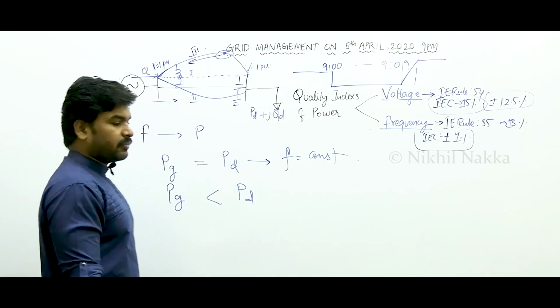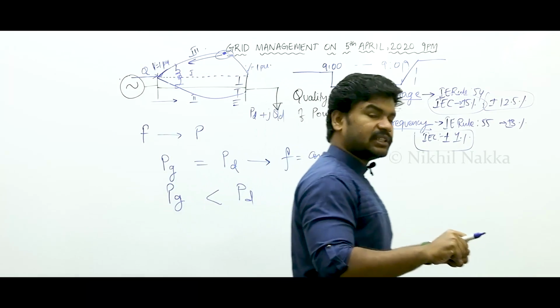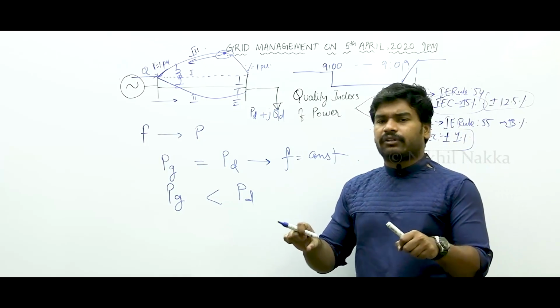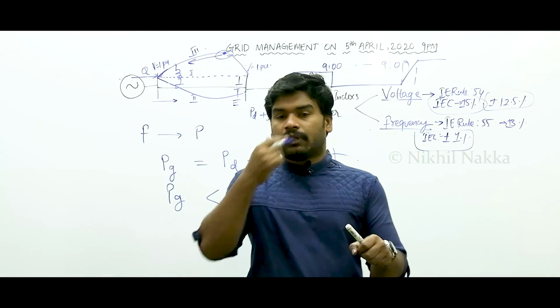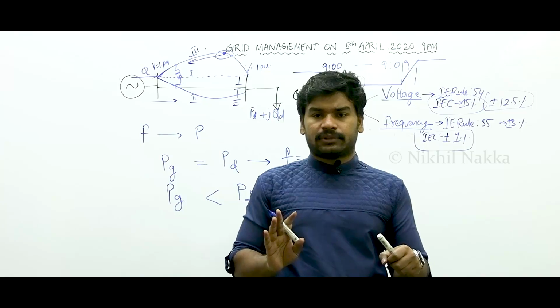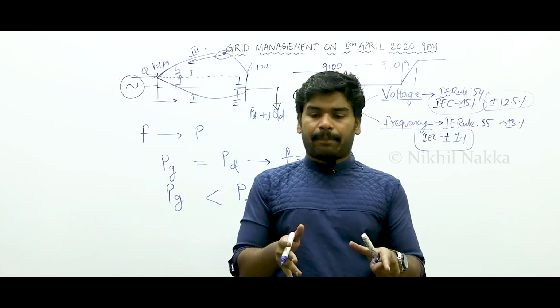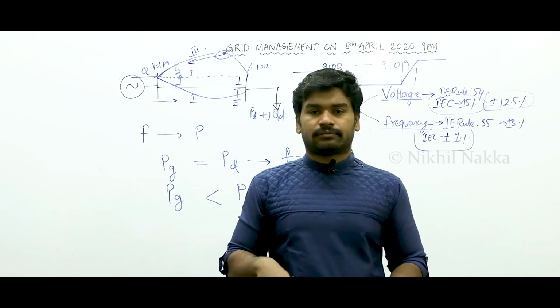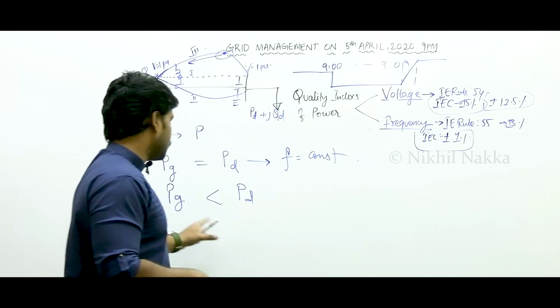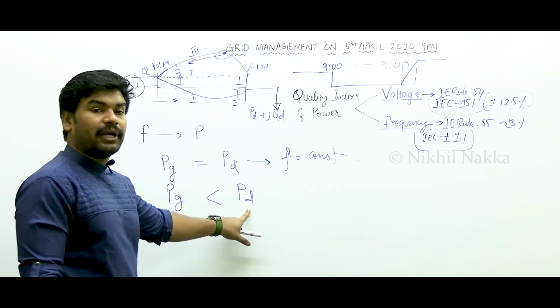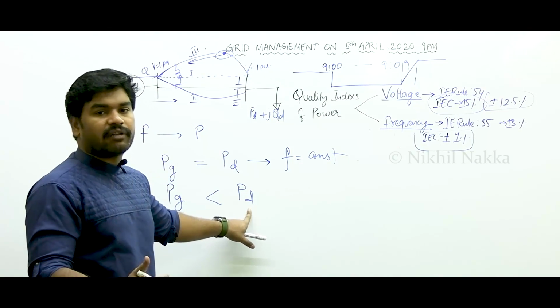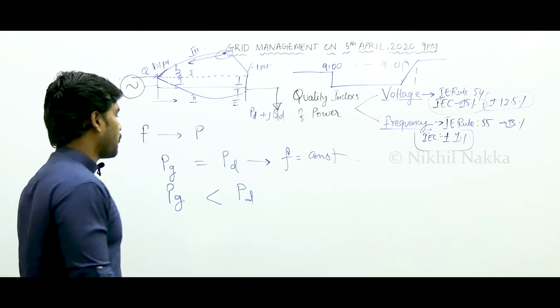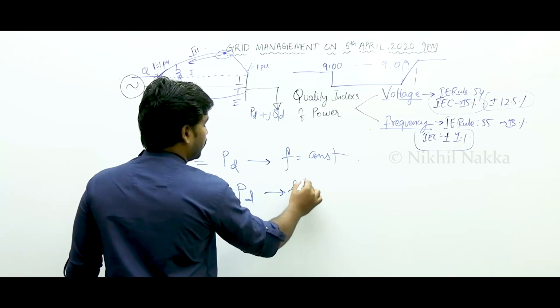More demand is there. Let us say you are going on a bike with constant acceleration, accelerator at some fixed position. Initially 2 members on the bike, suddenly 4 members will sit - what happens to the speed? It will fall. That is what happens here: generation is less than demand, demand increases, speed of the generator will fall, frequency will fall. So this will lead to frequency drop.